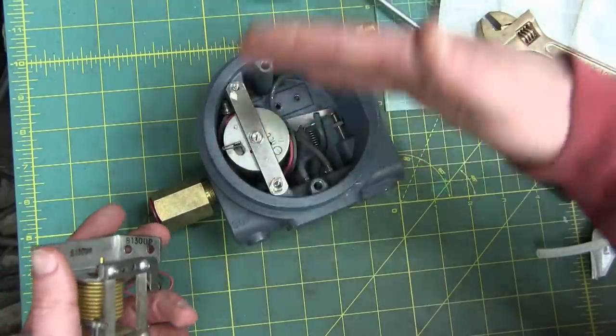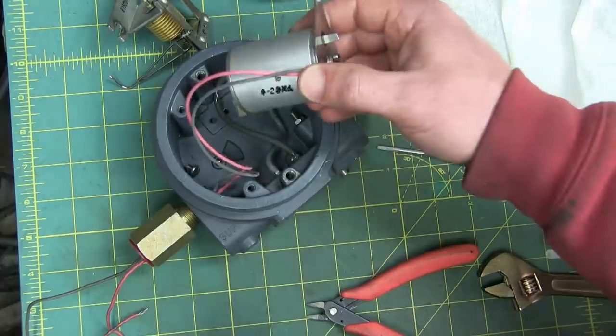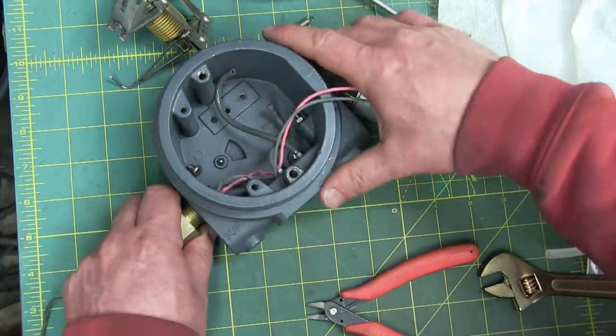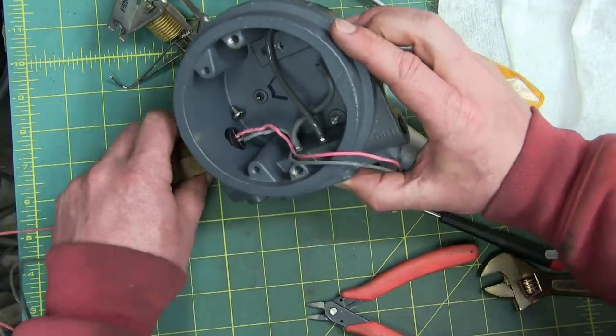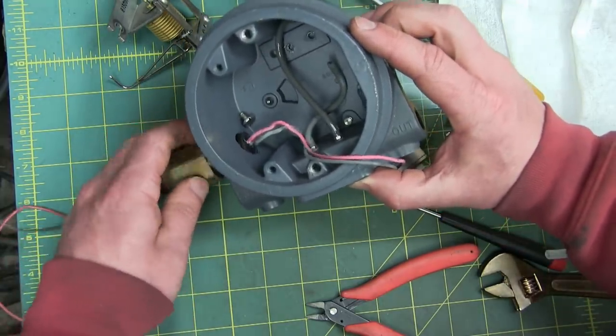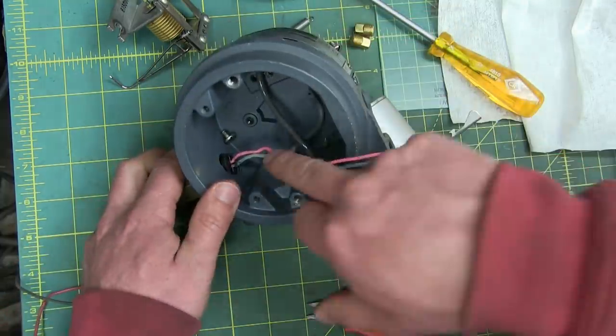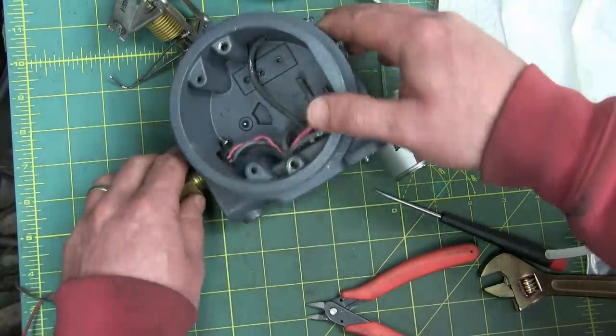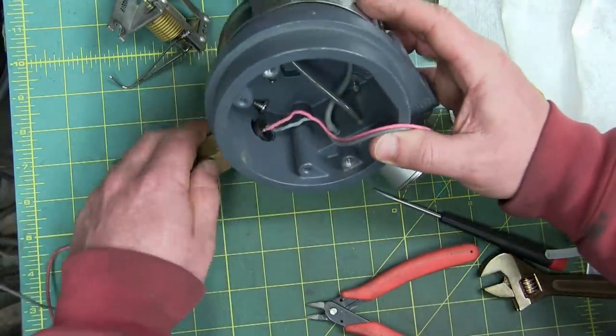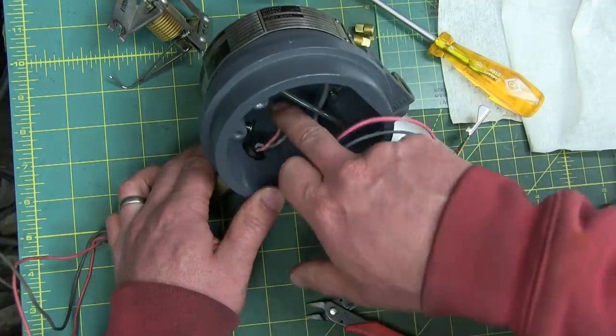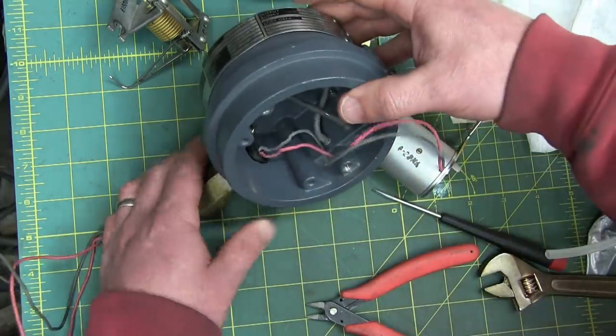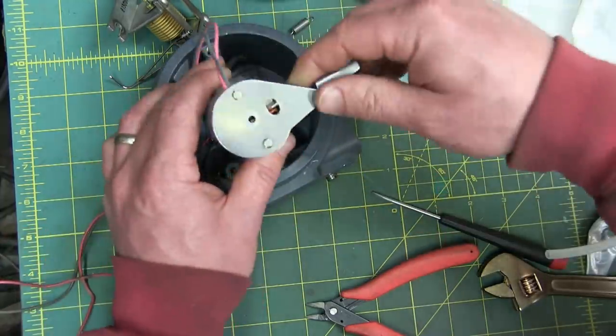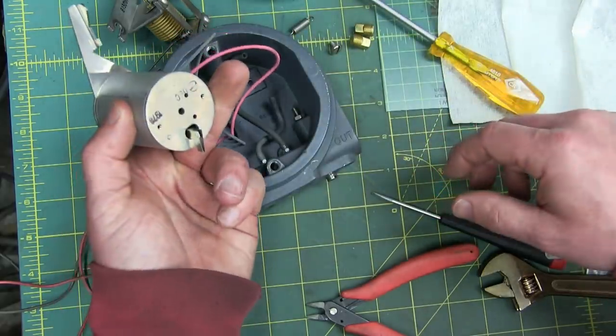We got the rheostat or what I'm calling the rheostat out. Just a wee bit of spring works. And we found the smoking gun. Students! They got their hands on this and beat the shit out of it. You can see because it's intrinsically safe, all the wires got to be sealed right up. And when you turn this gland in and out, it twists the wires up like a pretzel and eventually breaks them off. So that, I think, would be the best explanation as to why this thing no longer works.